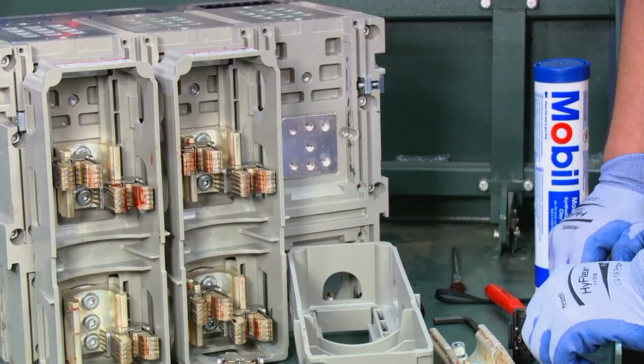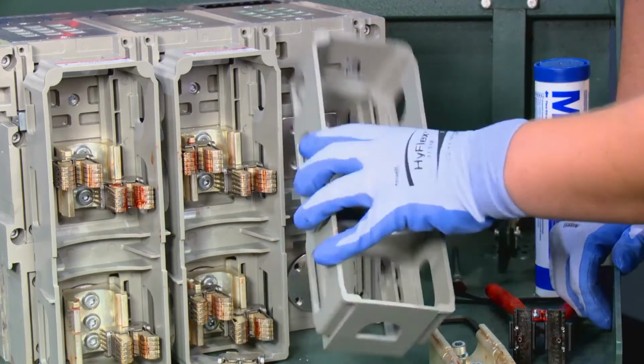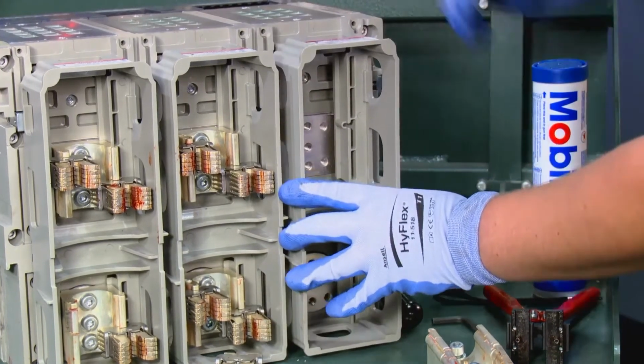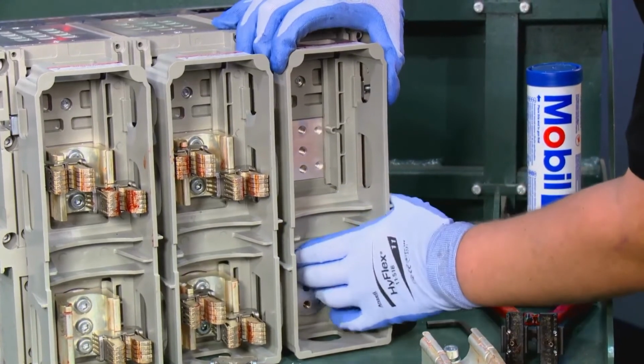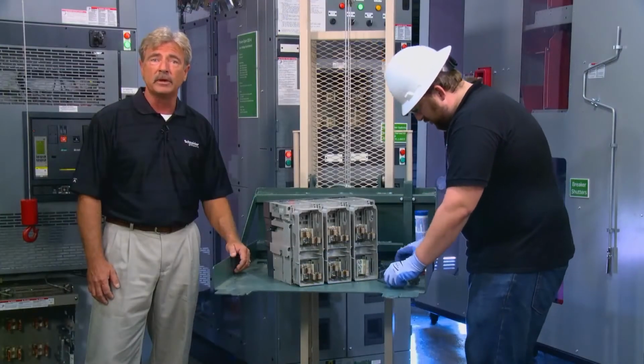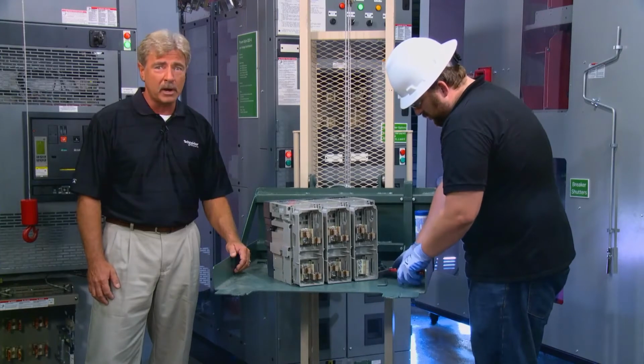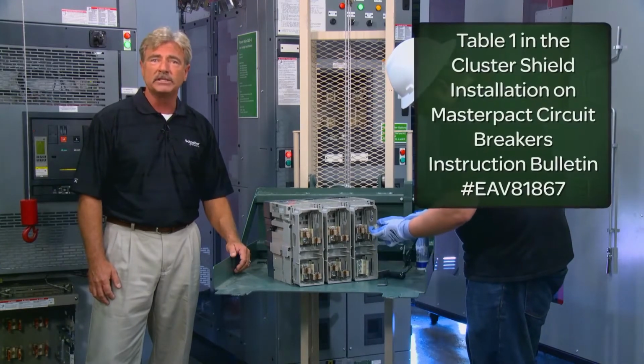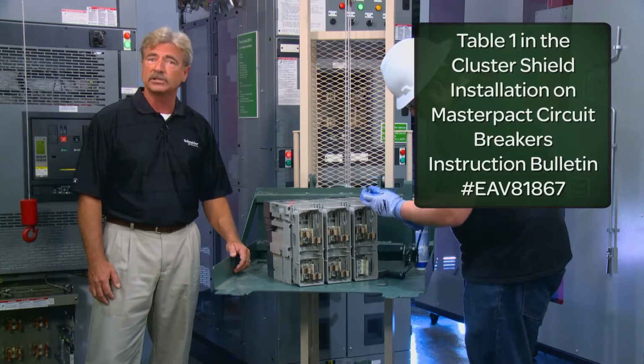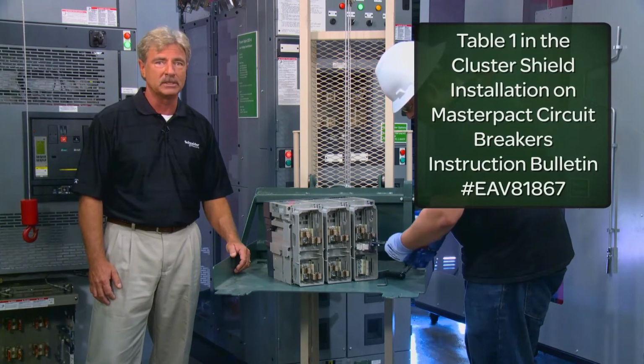As you can see, Brooks has removed the remaining cluster supports by removing the screws. Next, the cluster shields must be installed before installing the new cluster supports. So before moving forward, confirm that you're using the correct cluster shields by viewing Table 1 in the cluster shield installation on Masterpact Circuit Breaker's instruction bulletin.